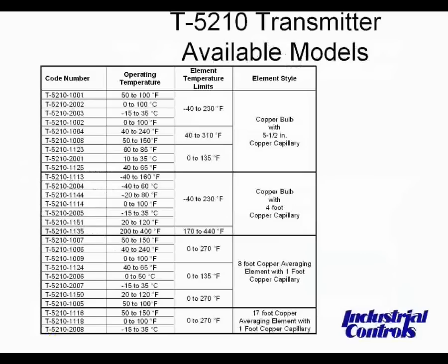This gives you a list of some of the Johnson Controls models and how many different variations there are. The operating temperature column is key: the first one says 50 to 100 degrees, another says 0 to 100 degrees, and one further down is 40 to 240. As mentioned before, the transmitter is chosen based on the conditions of where it is installed. Room transmitters are typically 50 to 100 degrees; 0 to 100 can read outdoor temperature or non-heated water; and 40 to 240 can read hot water temperature. These represent spans of 50, 100, and 200 degrees.